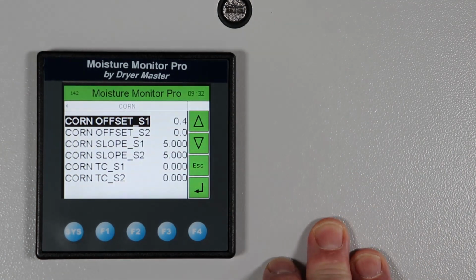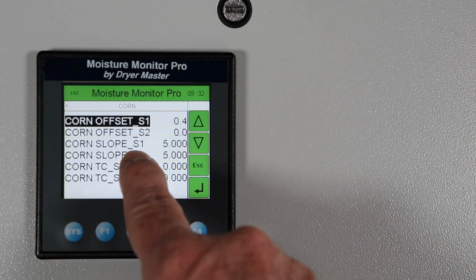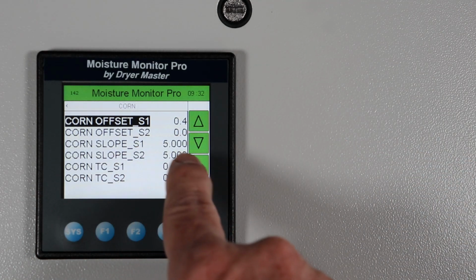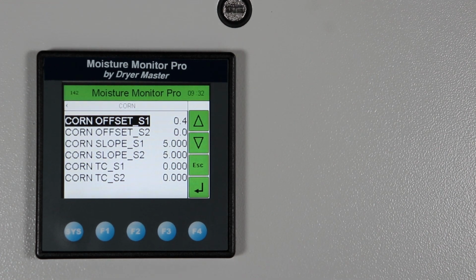So the value we're talking about here is the corn slope 1 slope sensor 1, corn slope sensor 2. We use 5 there, and that's pretty much a standard application for 56-pound corn. And so typically you won't have to change that, but there may be a point where you may want to change that if you're seeing some issues with calibration. You can always call us again at the support center at any time if you have questions about that. We can also look at your cal files that you can download to your USB if you have any questions. Now, typically you shouldn't have any problems, but this is there as an option to make adjustments if we need to make them.